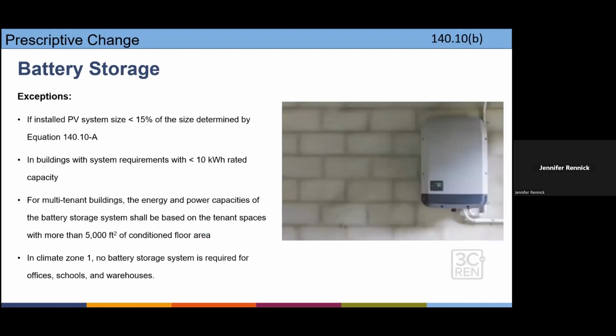And there are some exceptions for the batteries as well, so that if you end up with something less than 10 kilowatt hours, for example, you don't need to do the batteries. And if you happen to be working on a project that's in climate zone 1, there are no battery storage requirements for offices, schools, and warehouses, where that was determined not to be cost effective.